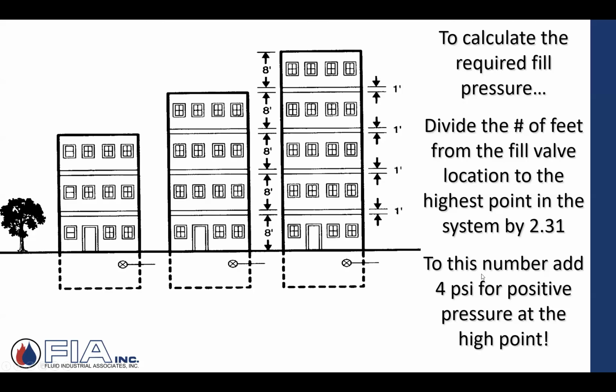And then this little statement here is very important to recognize. To whatever that number is, add 4 pounds. Because if I took that math and divided it by 2.31 and came up with a number, and I set that fill valve for that number exactly, what's the pressure up here at the high point? It might be 0. So I got the water up there under no pressure. I don't want that. I want positive pressure at the high point. If I have any vents on the high point, I want vents to vent. Vents vent into the atmosphere. That's 0 pounds gauge. If I have 0 pounds on the system side, 0 pounds on the outlet, there's no motive force. I'm not doing anything. So industry standard says, whatever it takes to get there, divide it by 2.31, and then to that number, add 4 to 5 pounds. Now I know at the high point, I'm pressurized all the way up.